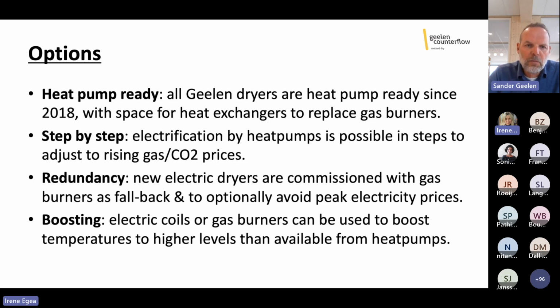We also make it possible for them to do a step-by-step electrification. So in the example that I showed you before, where there are 2 heat pumps, you could actually start with only 1 heat pump in the lower temperature zone, which has the highest COP, and therefore do a recovery of energy and money on the low temperatures first, and then add heat pumps step by step on the way. So that makes it financially more attractive to do a phase out in steps.